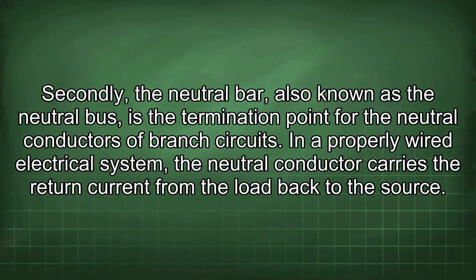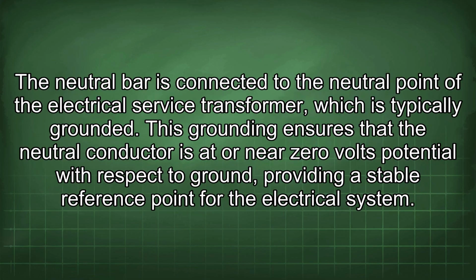Secondly, the neutral bar, also known as the neutral bus, is the termination point for the neutral conductors of branch circuits. In a properly wired electrical system, the neutral conductor carries the return current from the load back to the source. The neutral bar is connected to the neutral point of the electrical service transformer, which is typically grounded. This grounding ensures that the neutral conductor is at or near 0 volts potential with respect to ground, providing a stable reference point for the electrical system.